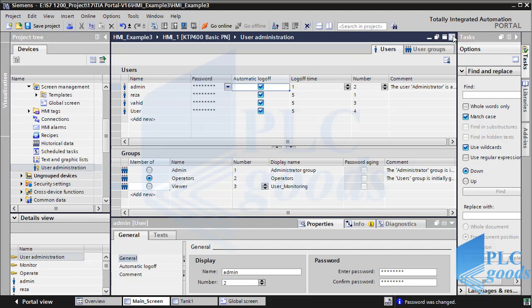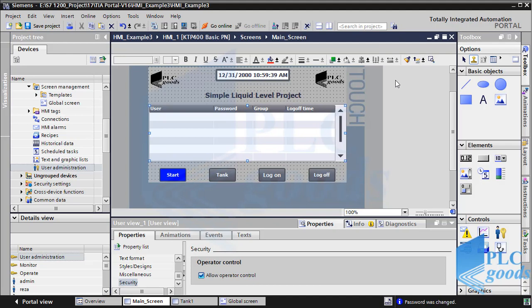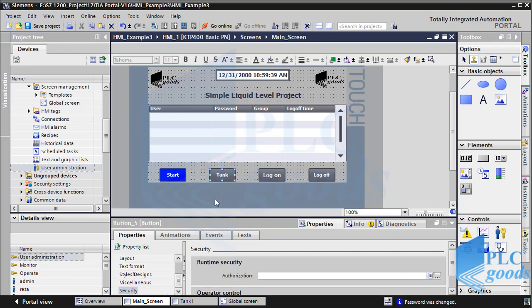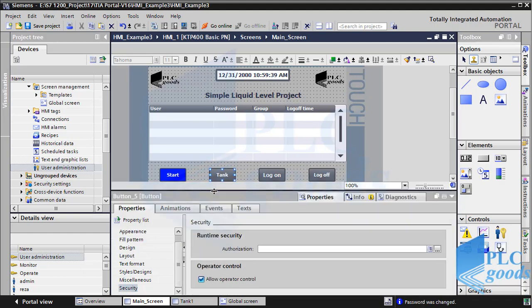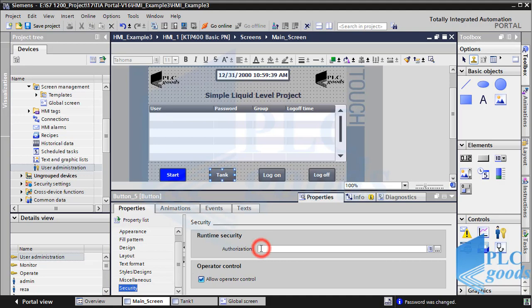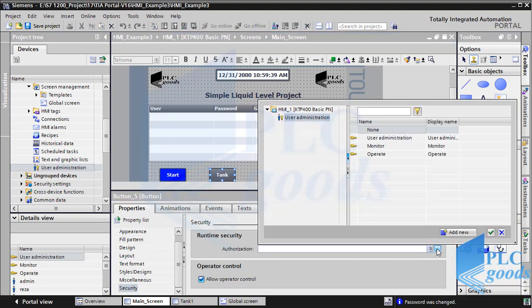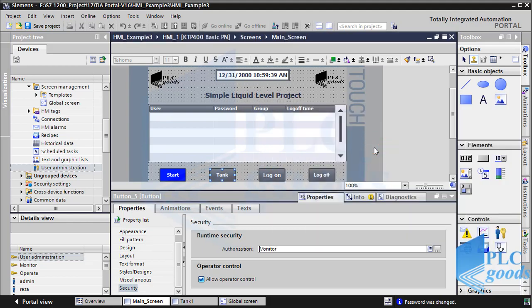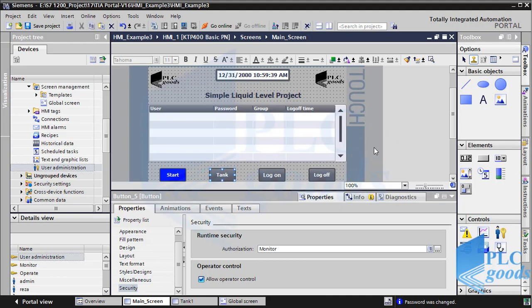Let's go back to the HMI screens. The HMI starts with this screen, so everyone can see it. Suppose just the four defined users are allowed to see the tank screen. So we must go to the security part of this button. Here we must determine which authorization the selected button requires. I select monitor authorization — if you remember, all three defined groups have monitor authorization, so four defined users can work with this button and go to the tank screen, but others cannot.